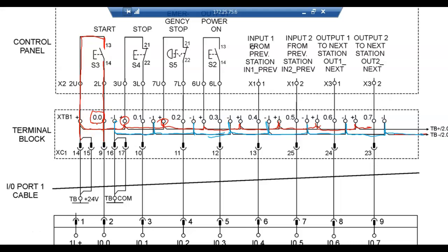So on our terminal boards, 0, 1, and 2 are inputs, 4 and 5 are outputs. That's the way they're labeled on terminal boards. And then this would come down into our PLC, and you can see it goes to input 0.0, and there's an LED there. That indicates that when I press that start button, you should see the LED on my PLC go true. So what I just did is use my PLC to check my push button to see if it's okay, then check to see if it's getting all the way to the PLC. So those indicator lights on the front of that PLC are extremely valuable for troubleshooting.